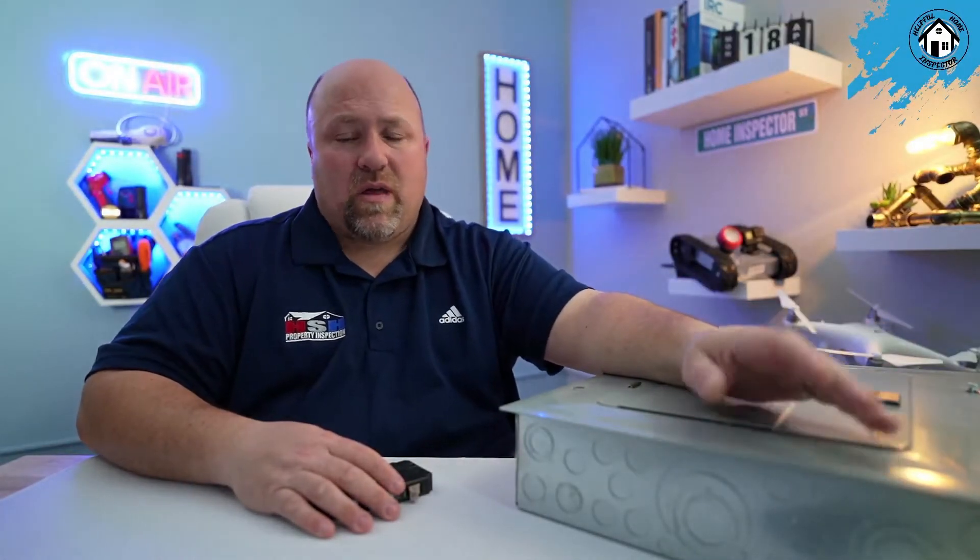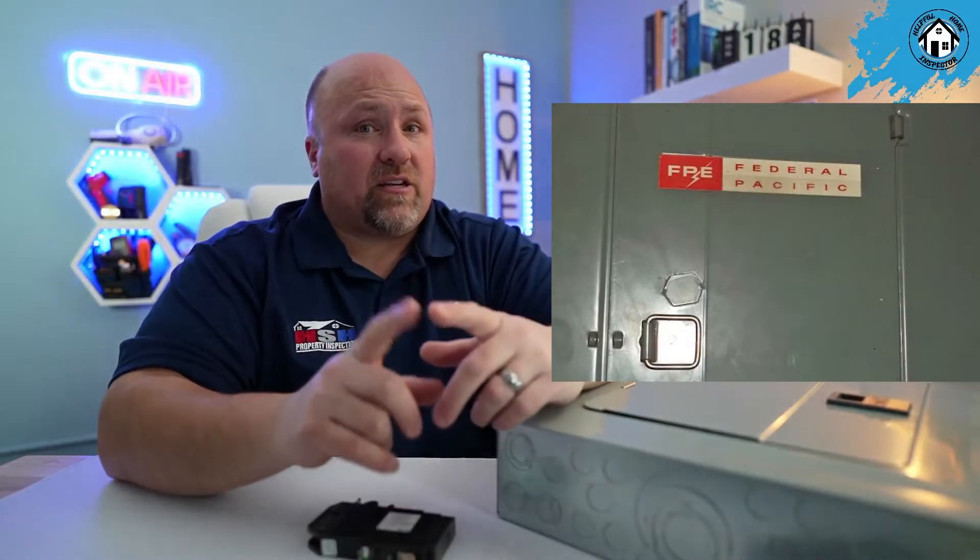In 2002, Federal Pacific was found guilty of producing breakers with false UL listings — claiming a certification they did not have, giving a false sense of safety to purchasers. There were lawsuits, but there was never an overall product recall, which there probably should have been. As a home inspector, when you take the panel off, breakers can fall right out — that's just not acceptable. Federal Pacific Stab-Lok breakers need to be removed immediately; they are a major adverse defect. Look for the orange and silver tag on the panel.